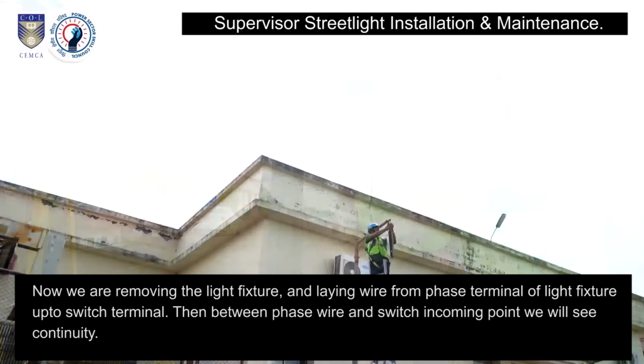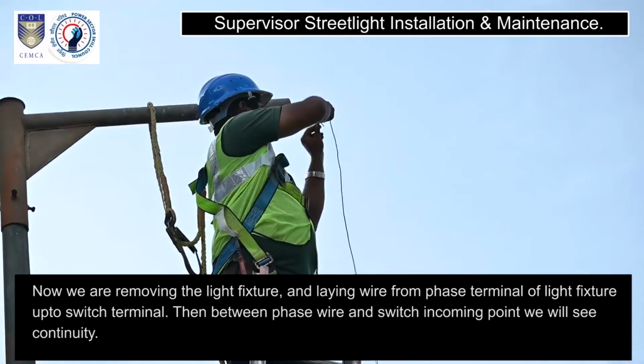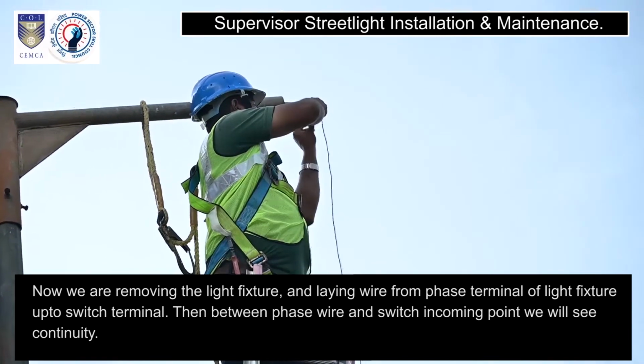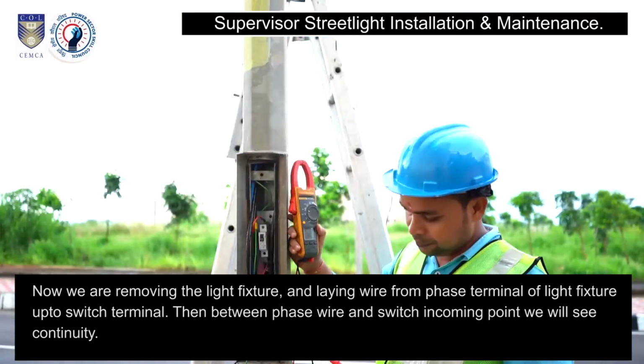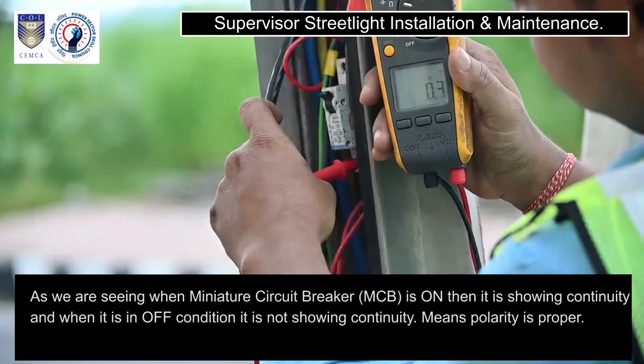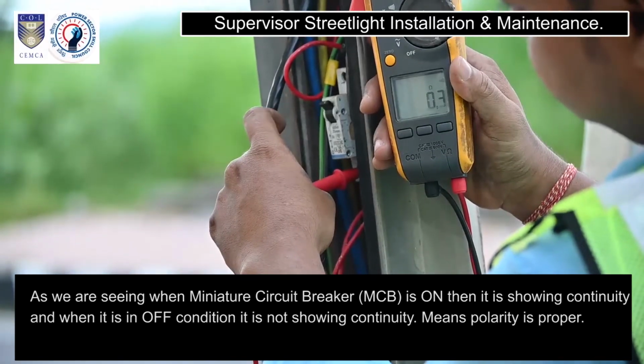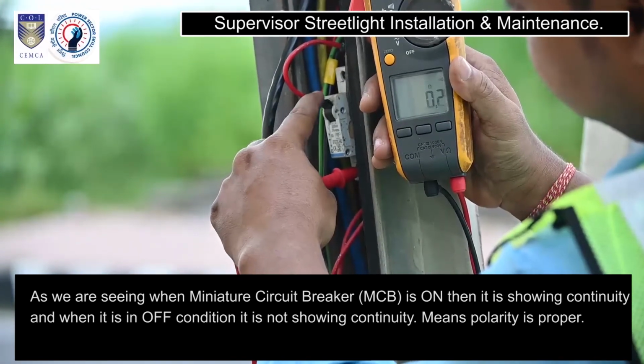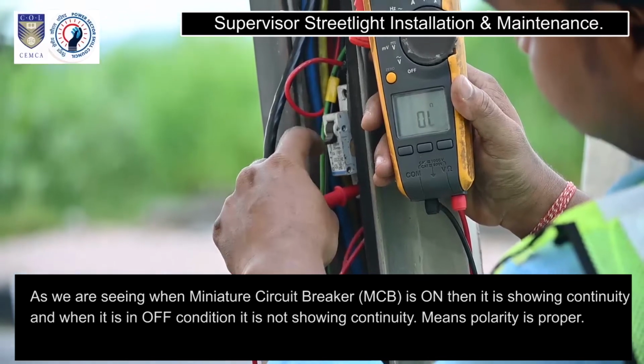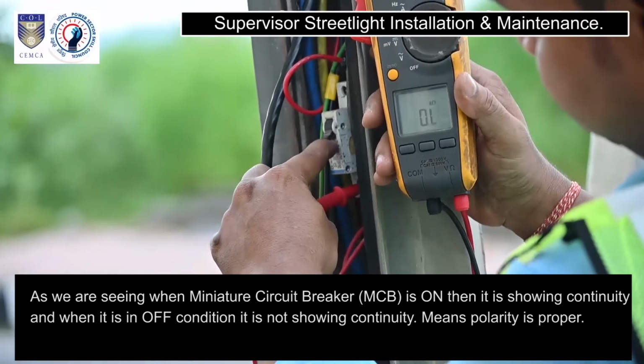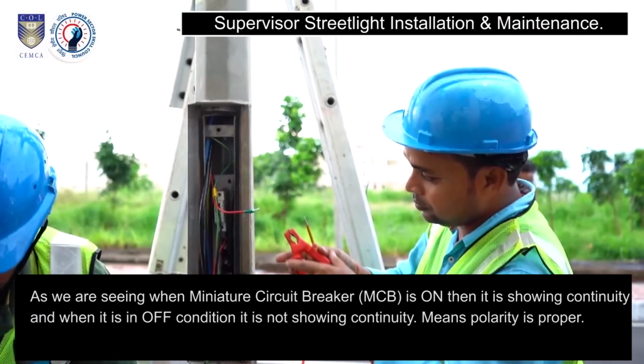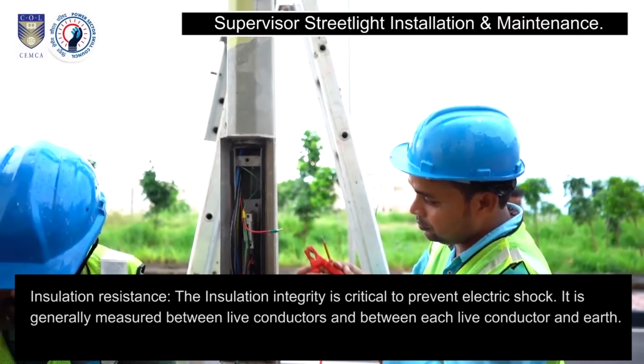Now we are removing the light fixture and laying wire from phase terminal of light fixture up to switch terminal. Then between phase wire and switch incoming point, we will see continuity. As we are seeing when miniature circuit breaker MCB is on, then it is showing continuity, and when it is in off condition, it is not showing continuity. Means polarity is proper.